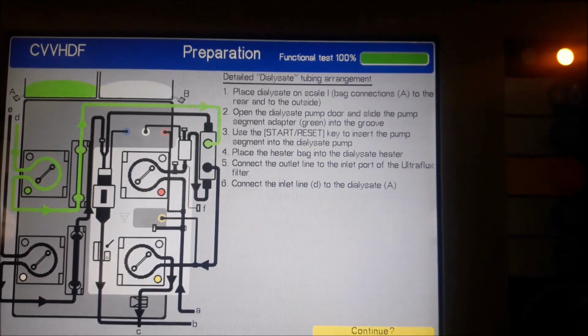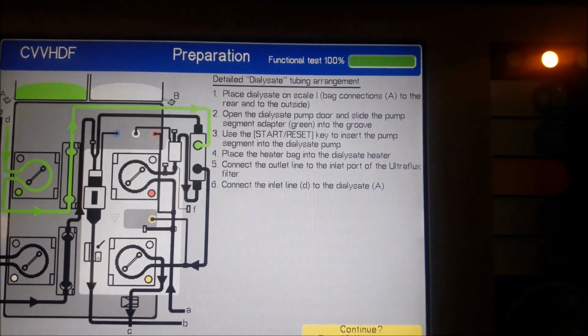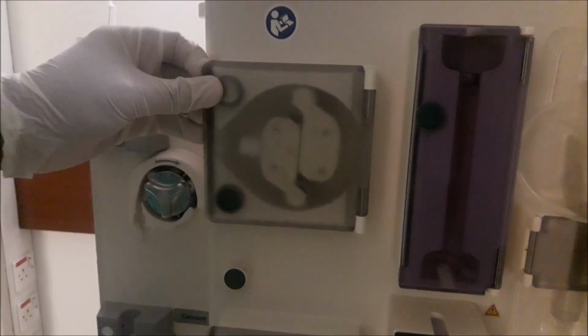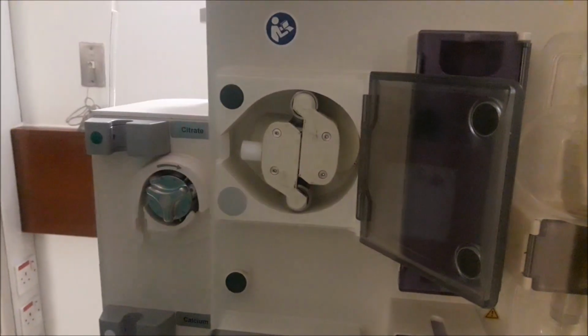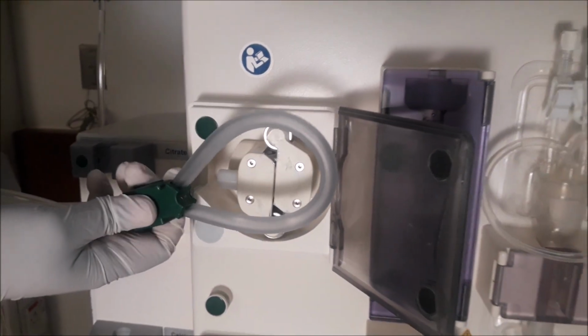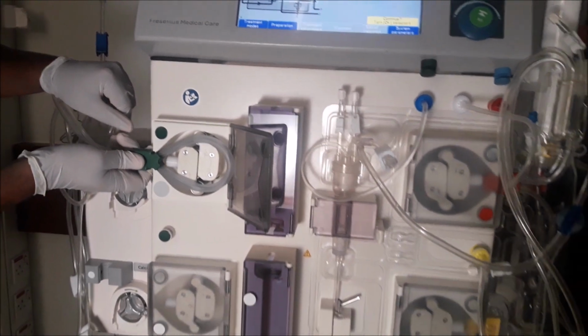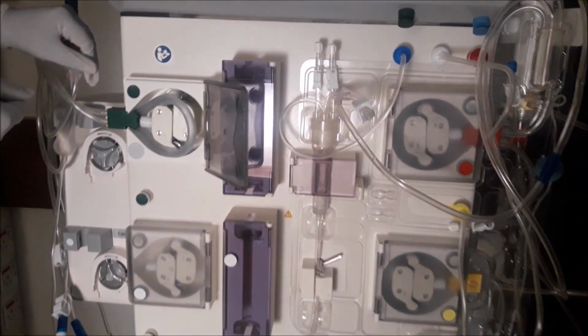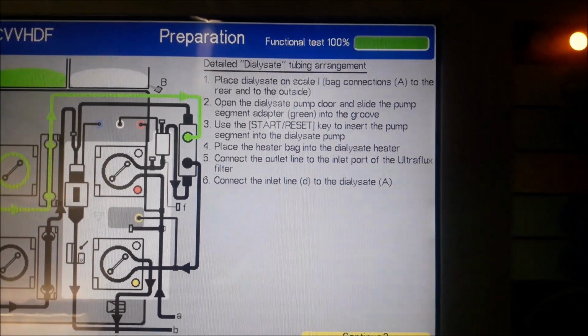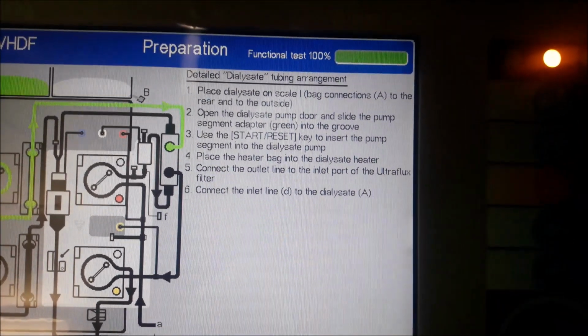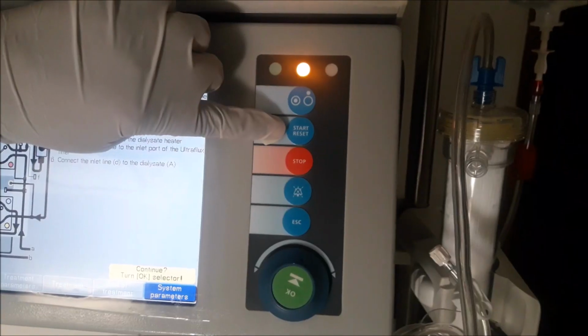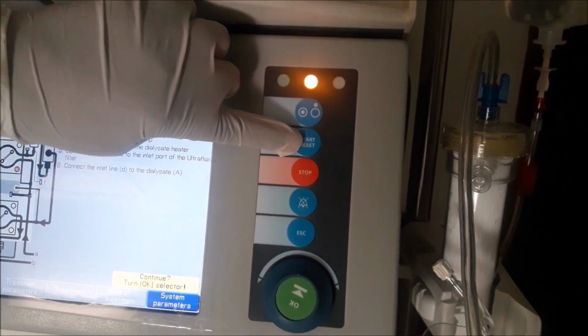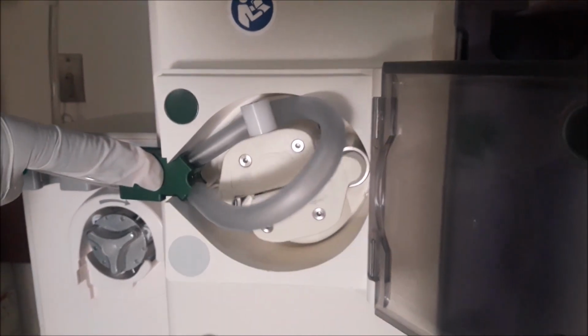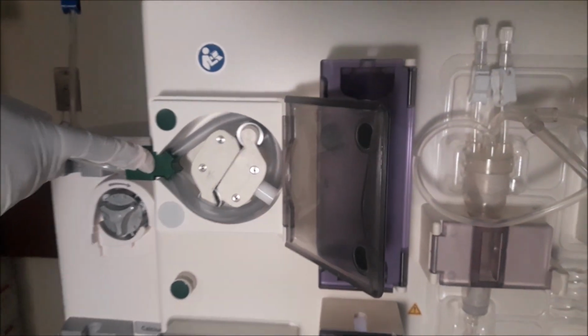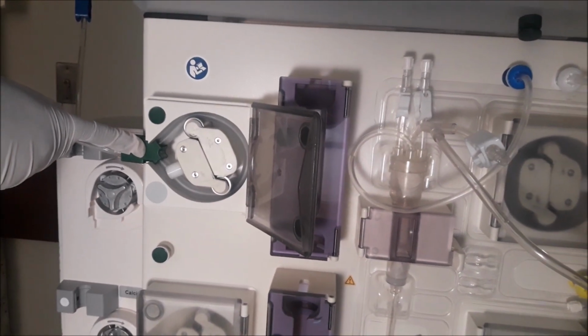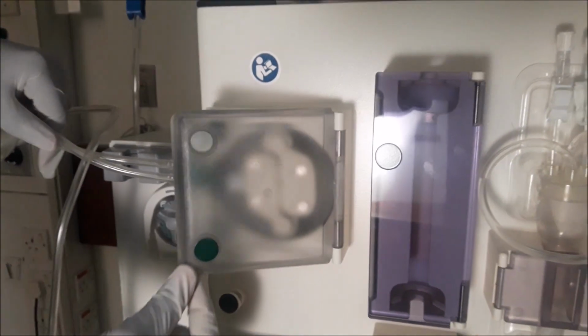Point 2. Open the dialysate pump door and slide the pump segment adapter, green, into the groove. Opening the dialysate pump. Now we are inserting the dialysate tubing into the dialysate pump. Use the start reset key to insert the pump segments into the dialysate pump. Press the start and reset key until the tubing of dialysate is fixed into the dialysate pump. Let's close the door and move toward the next step.